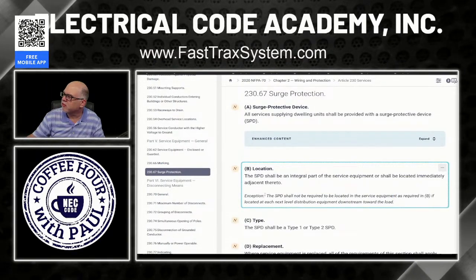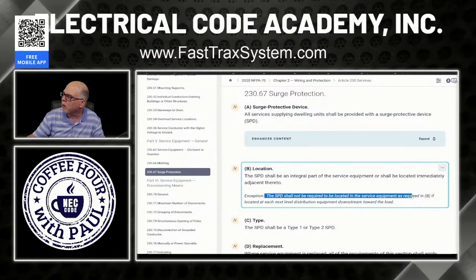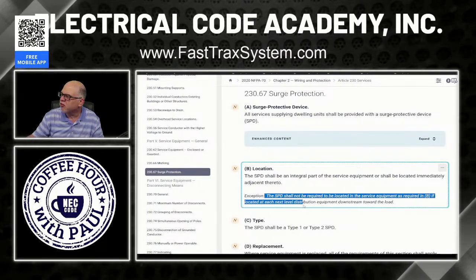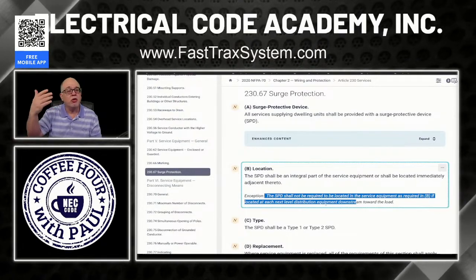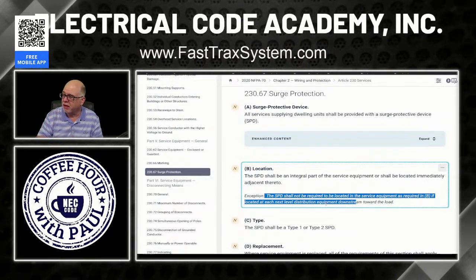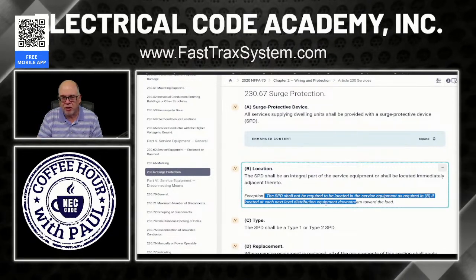So let me read that again. This SPD shall not be required to be located in the service equipment as required in B, which is what we just read, if located at each next level distribution equipment downstream towards the load. Okay, so you could have them at the actual dwelling units. How about that? And that would be fine. And it might be just a plug-in on the bus, keeping it simple. And that's probably the majority of how they're done today.